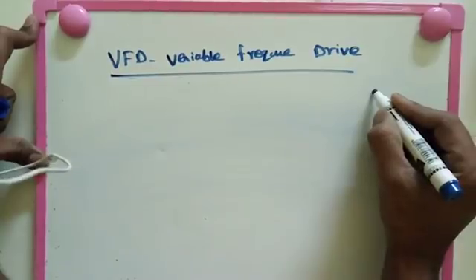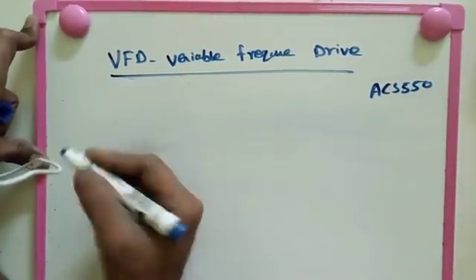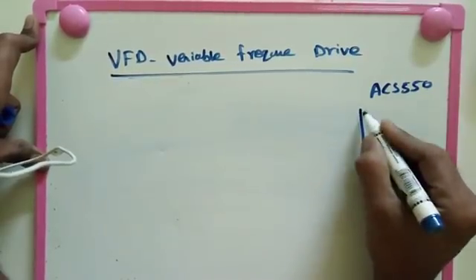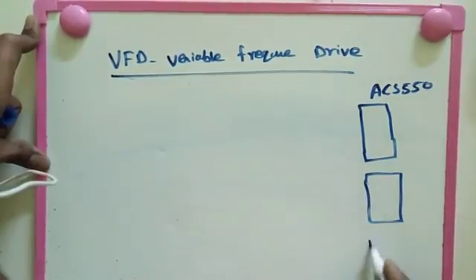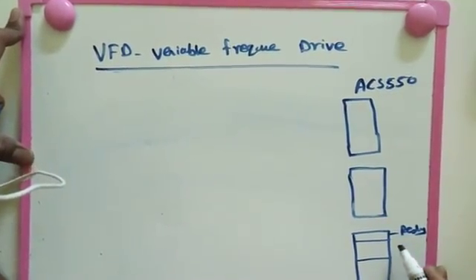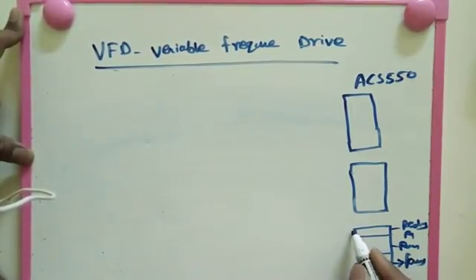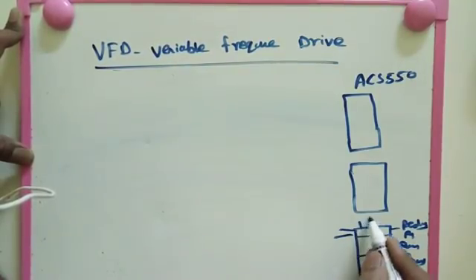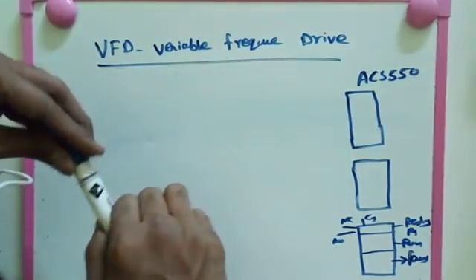Now we are taking the ACS 550 VFD as our example. This VFD has 27 terminals arranged in three groups of 9. We have three relay blocks: the first is the ready relay, the second is the running relay, and the third is the fault relay. Each relay has three terminals: common, NC, and NO.